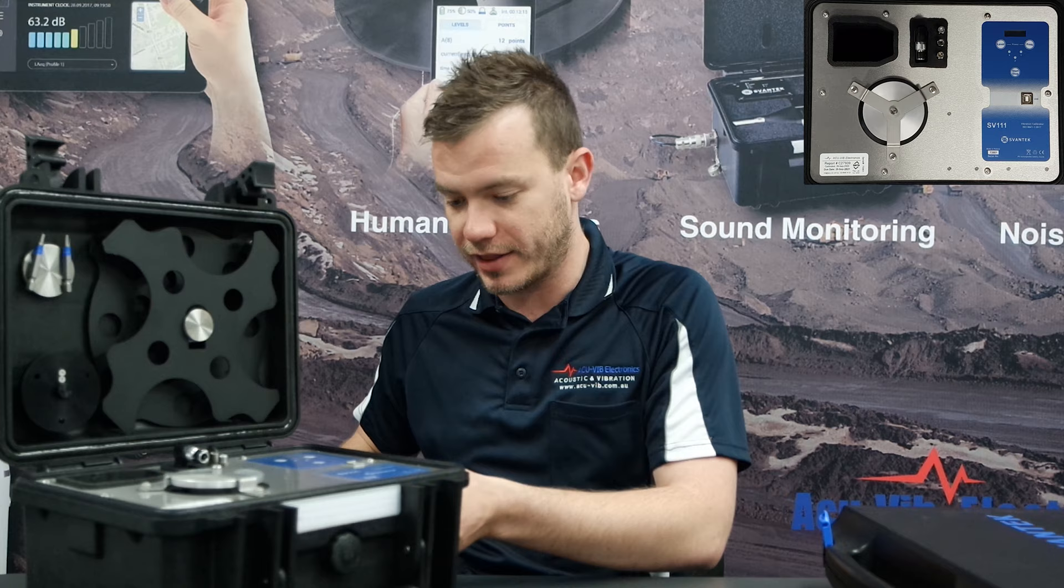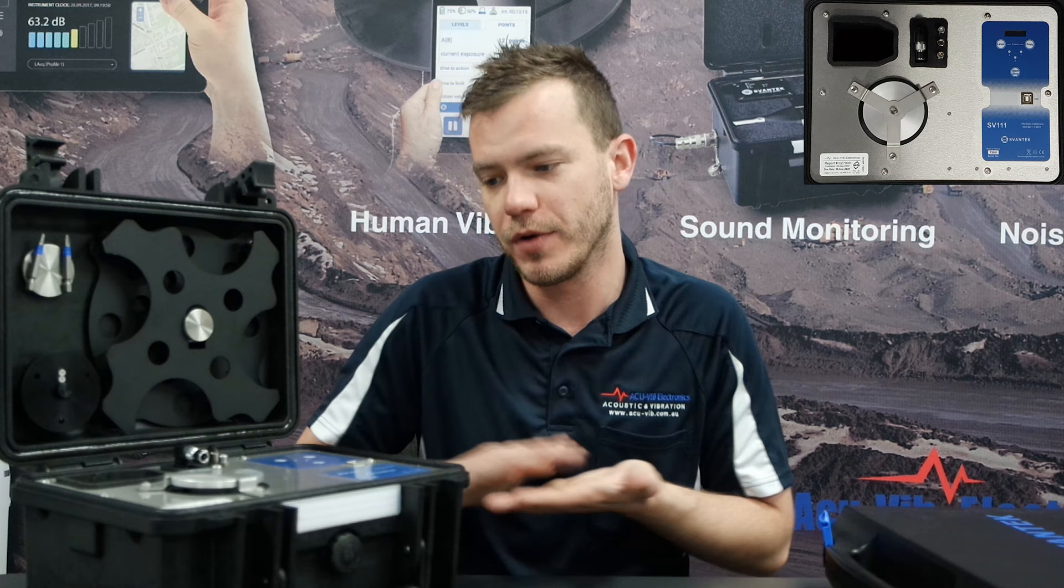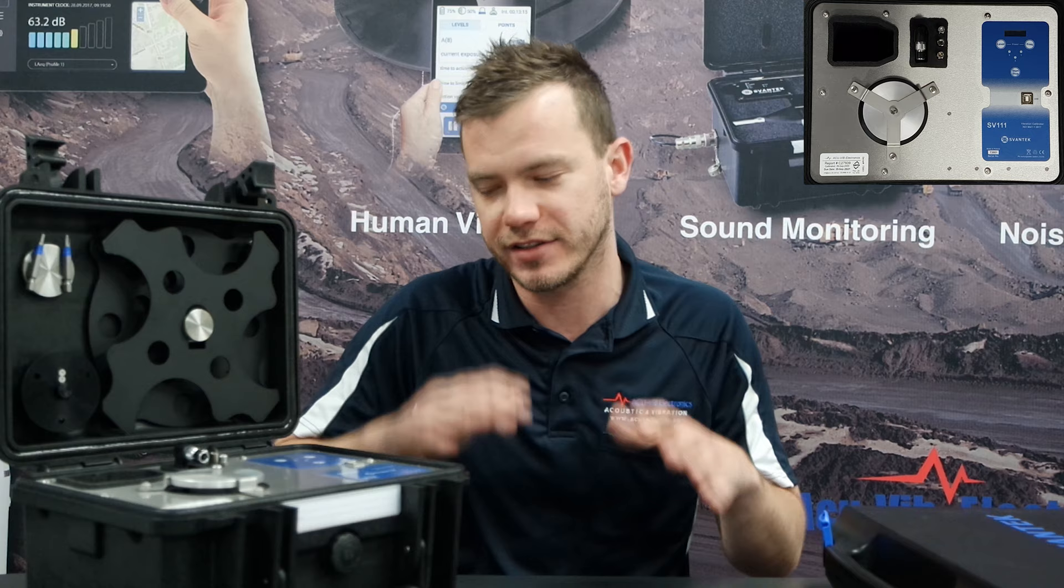First things first, we've got a mains adapter that goes into the side of the case, pretty straightforward. I've got enough battery now so I'm not going to use it. Please note when you're doing these sorts of measurements it has to be on a sturdy surface, so your office desk isn't appropriate. We do it on a thick tile for example to minimize vibration. There's an automatic level sensor in here that will tell you if your desk is moving around, but I just want to get started.